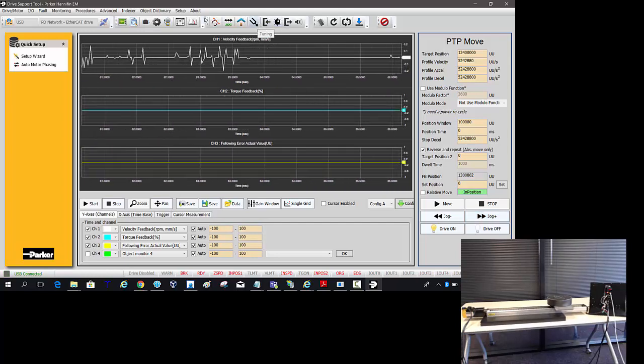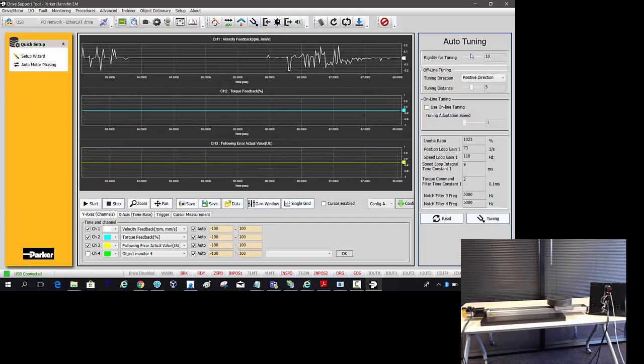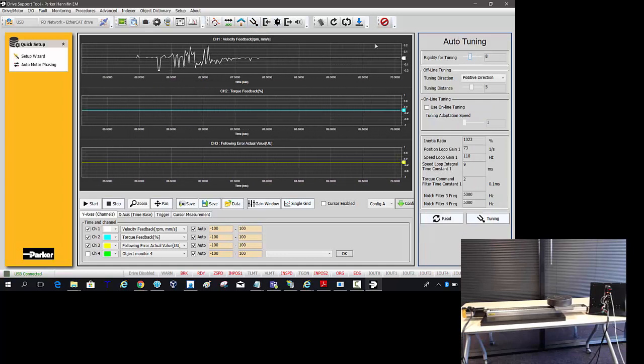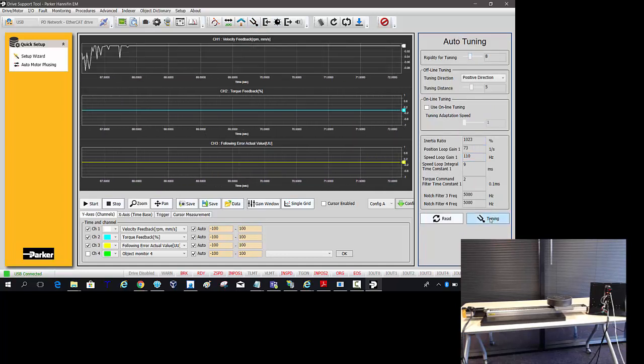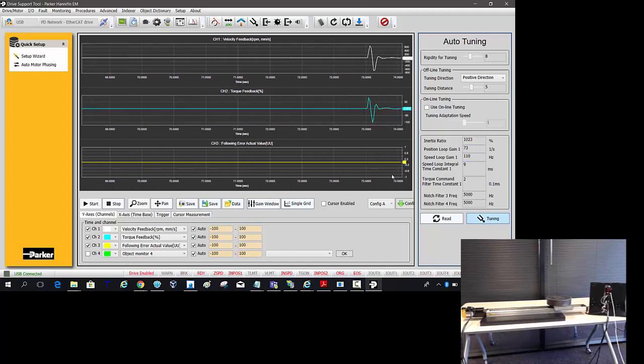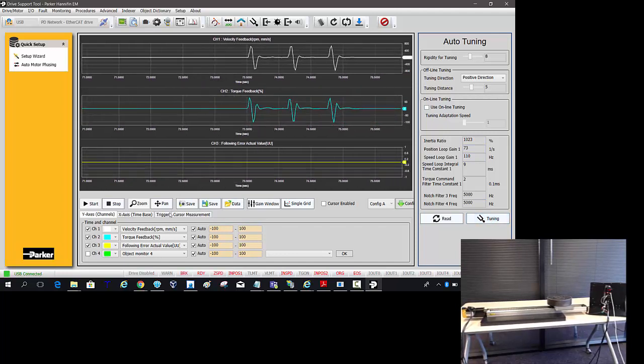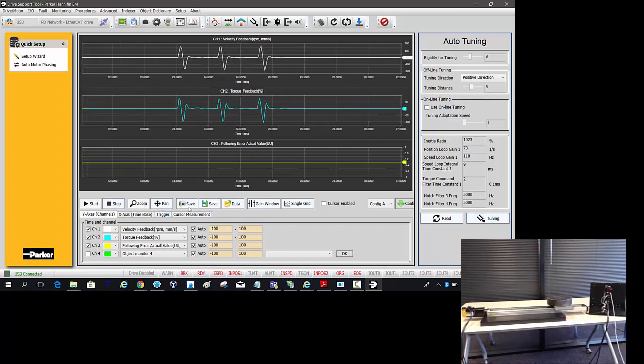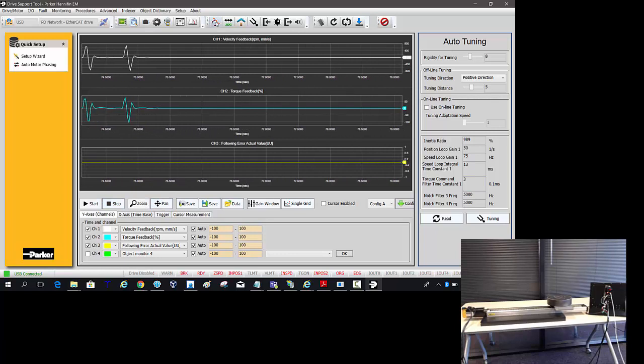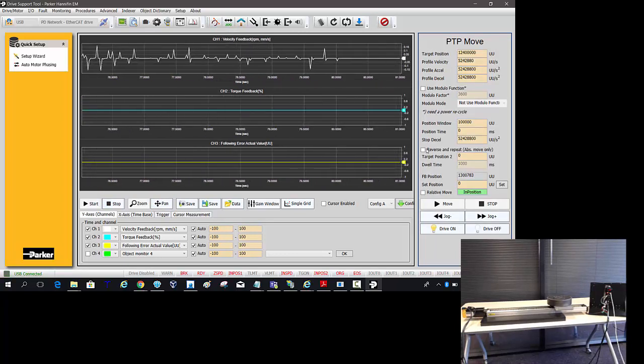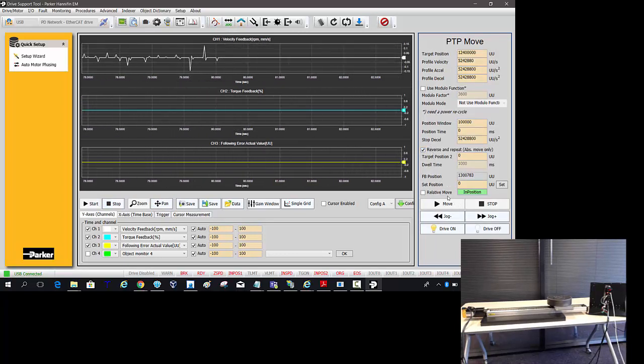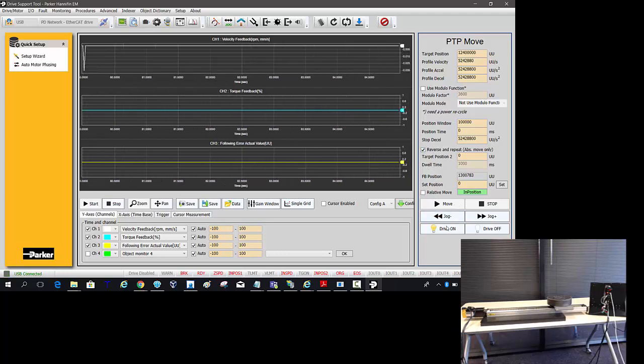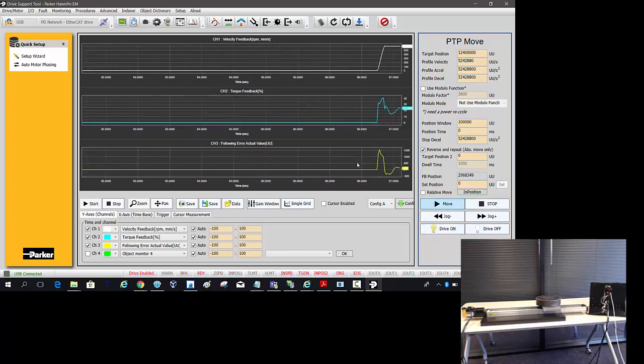So from here, want to take the rigidity and dial it down two notches down to eight. Re-do the tuning. And then go back into the point to point move, reverse and repeat, enable the drive, and then move again.